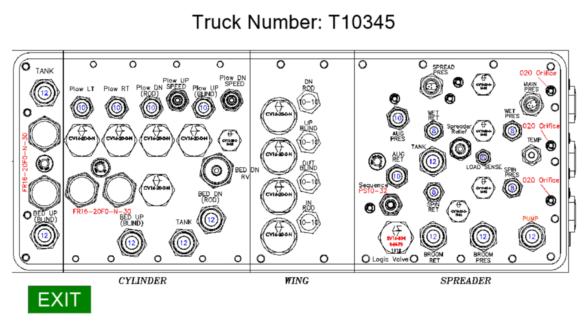In addition to these documents, the coil energization screen shows, in real time, which coils are energized. Tests can be done without the truck running, eliminating the dangers of a pressurized hydraulic system. A small wrench or screwdriver is used to check that the correct coils are magnetized for a given input. If they are, the problem is likely hydraulic. If not, it's in the controls. This helps safely solve the trickiest part of any electrically controlled hydraulic troubleshoot.